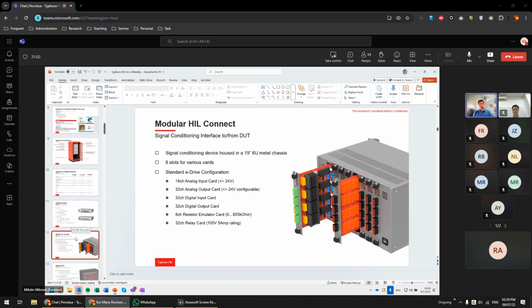Just to briefly touch on the modular HIL Connect, our signal conditioning interfacing device: it comes in a 6U metal chassis and can fit up to 8 different cards in one device. For the standard eDrive configuration, we have an analog output card with a range of plus minus 24 volts, a digital input card, digital output card, a resistor emulation card to simulate temperatures, and a relay card.